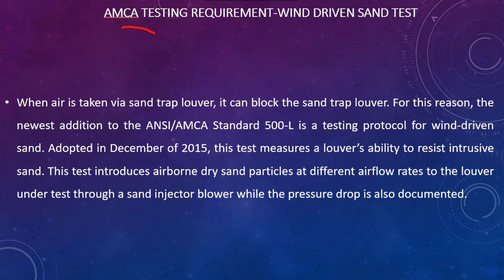The AMCA testing requirement for the wind-driven sand test is one of the most important tests for the sand trap louver. When air is taken via the sand trap louver, it can block the louver. For this reason, the AMCA standard 500L has a testing protocol for wind-driven sand, adopted in December 2015, and this test measures the louver's ability to resist sand.